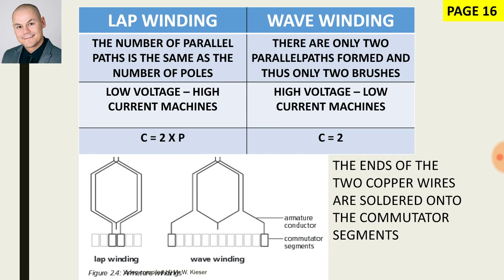Lap winding and wave winding — our armature can be wound in two ways, either lap or wave. For lap winding, the letter L tells us it is used for low voltage, high current applications, whereas wave winding is used for high voltage and low current applications. For a wave-wound armature, the number of parallel paths (C) is always two, whereas for lap winding the number of parallel paths is dependent on how many pole pairs there are.